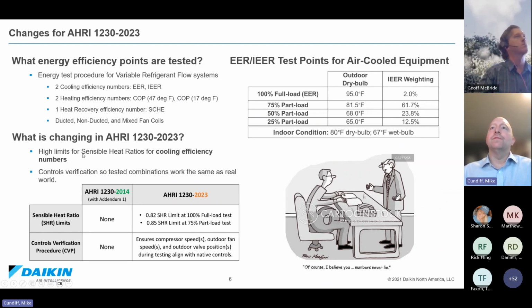Basically, you have high limits for sensible heat ratios for cooling efficiency numbers. So in the past, manufacturers could game it a little bit and put in higher sensible heat ratios, meaning drier room air that they're testing it in, which artificially bumped up the efficiencies that they were able to publish with the test standard. With the new one, there's going to be high limits for sensible heat ratios, meaning you're going to have a more humid, more realistic room that you're testing the indoor units in, which will make everything more of a level playing field as far as what the manufacturers are testing to.